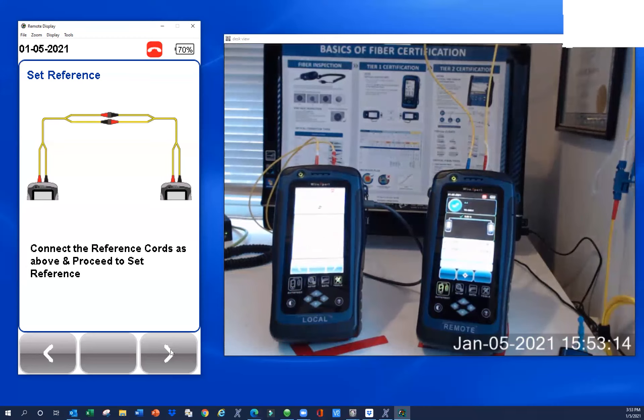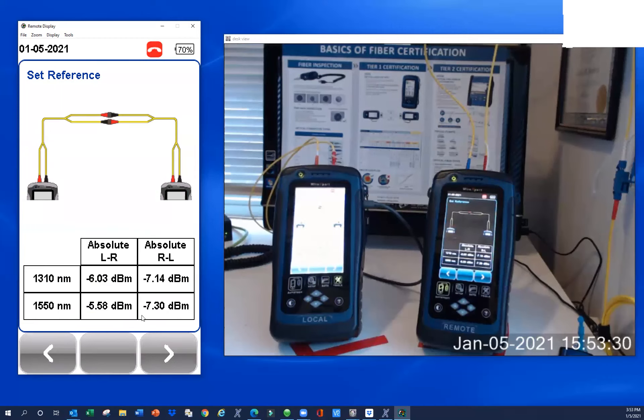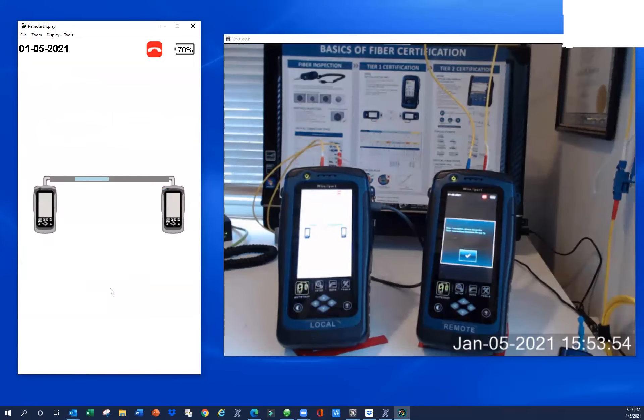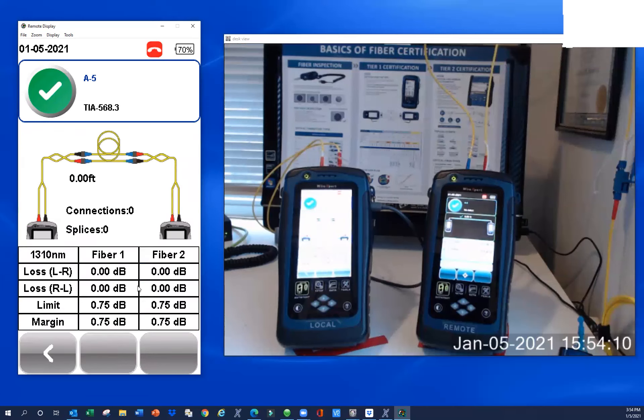We're going to hit the Go button. With single mode, you're looking for values between negative three and negative nine — that's different from multimode values. These are negative numbers because this is absolute power being sent back and forth. As you can see, we're between negative three and negative nine, so we're good to go. There's the message you get when you do a bidirectional test. We've referenced out most of the jumpers between the testers, so you wouldn't expect to see much loss. And we've got essentially zero loss in both directions — basically 0 dB at 1310 and a hundredth at 1550, which is fine.